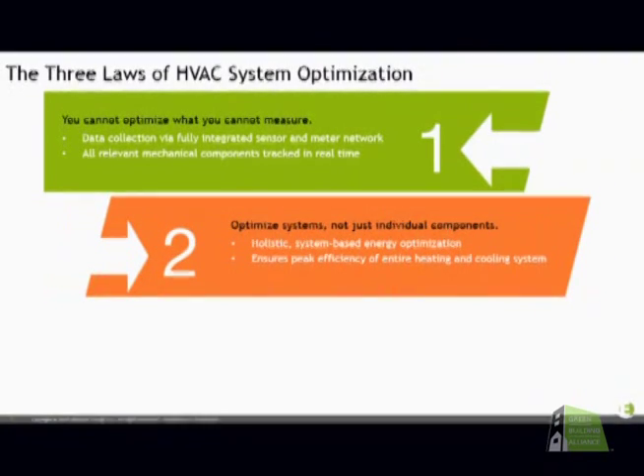Number 2, optimization of HVAC systems does not focus on individual pieces of equipment. This is really, really important. And it gets back to the point of doing more with what you have. This is not retrofitting pieces of equipment to a more efficient piece of equipment. You have an old boiler that has an efficiency of 80%. You replace it with a modern condensing boiler with built-in economizer that's coming out at 88 to 92, depending on the return water temperature. So you've gained efficiency just with a retrofit. That's not what this is.